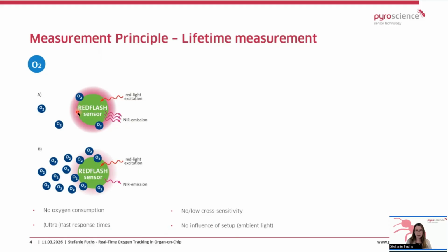So if there is a low oxygen level, the luminescent intensity is high. And if you are at higher oxygen levels, the indicator will be quenched by the oxygen, and then you get lower luminescence intensity, but also the lifetime of the luminescence will change. The good thing about this is that this measurement principle does not consume the oxygen, unlike electrochemical sensors would do, and also it is very, very fast. And due to the red light and near infrared, it does not interfere with a lot of things.